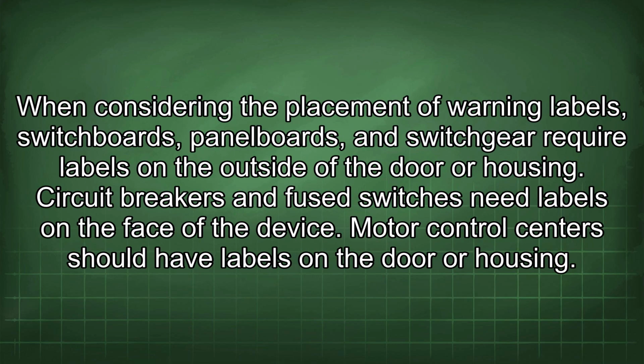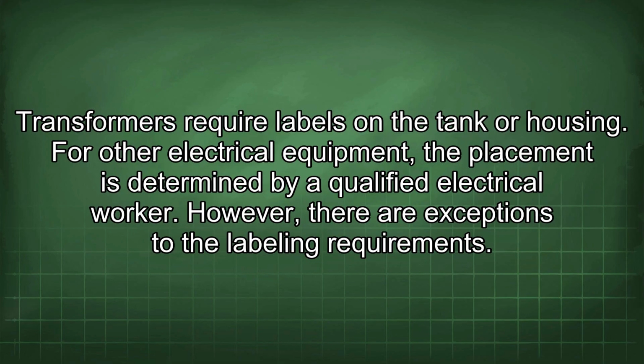When considering the placement of warning labels, switchboards, panel boards, and switchgear require labels on the outside of the door or housing. Circuit breakers and fused switches need labels on the face of the device. Motor control centers should have labels on the door or housing. Transformers require labels on the tank or housing. For other electrical equipment, the placement is determined by a qualified electrical worker.